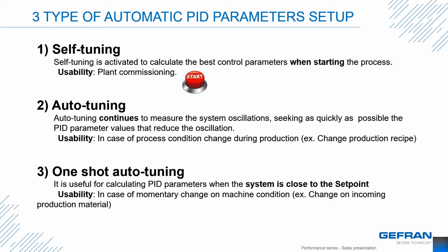As the name suggests, it happens only when the user commands it to begin. Auto-tuning, use this one for changing process conditions or settings. This allows quick adjustment to the PID as the process changes. This one's a good concept but some processes may have difficulty with the ever-changing conditions. And this happens, in either the self-tune or the one-shot auto-tune.